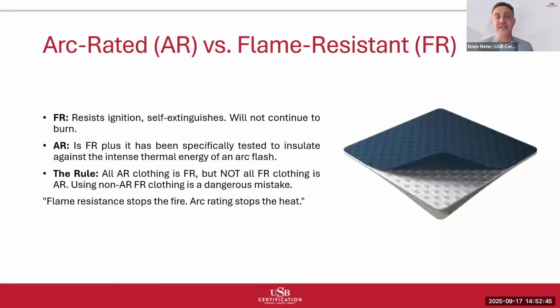Arc-rated and flame-resistant. This distinction is absolutely critical for safety, yet it's frequently misunderstood in the field. Let me explain the difference between flame resistant and arc-rated materials.